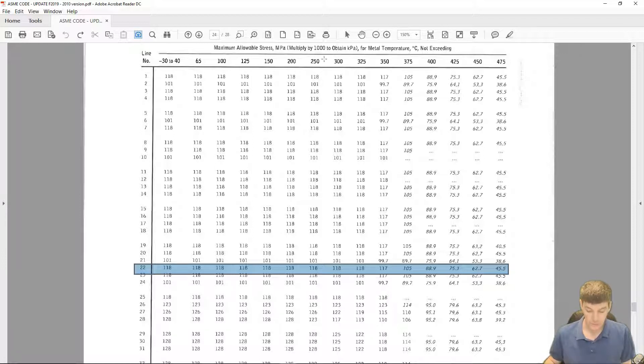If we keep going down then, line 22, we can scroll across and find at our temperature - and I believe our temperature was 280 degrees. Now we run into a problem. 280 isn't listed on our table. So what we would want to do is always round up to the next highest temperature. So in this case, 300 degrees, and we'll find our value. Line 22 and 300 degrees gives us a stress value of 118.